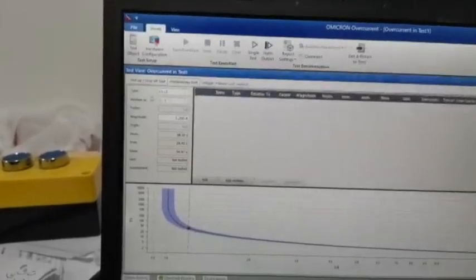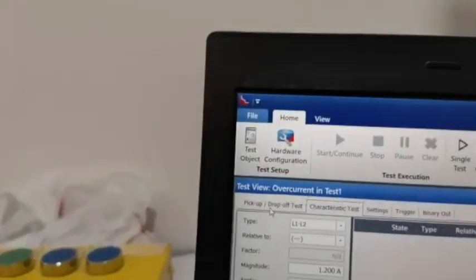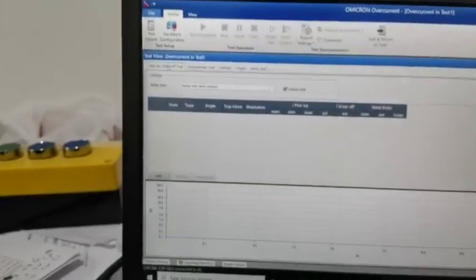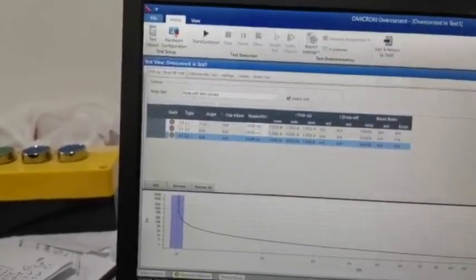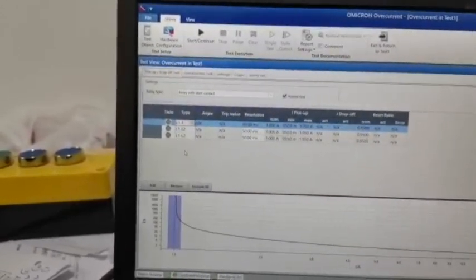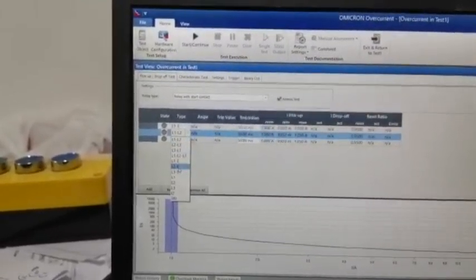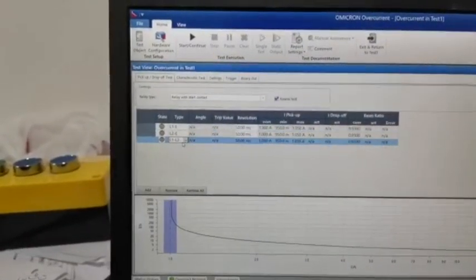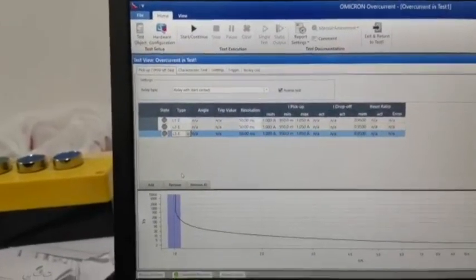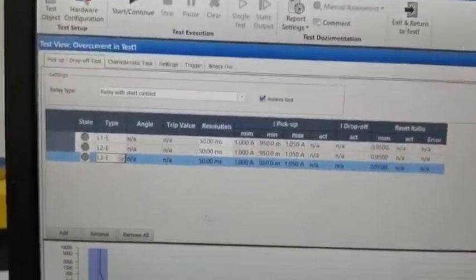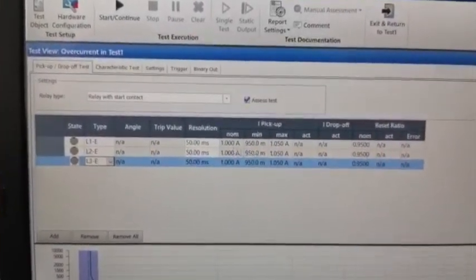Here you see the pick up and drop-off test. You can select add. Now we test one by one for each phase - L1, then L2, then L3. Our setting is one amp nominal, with minimum and maximum values, and reset ratio at 0.95.